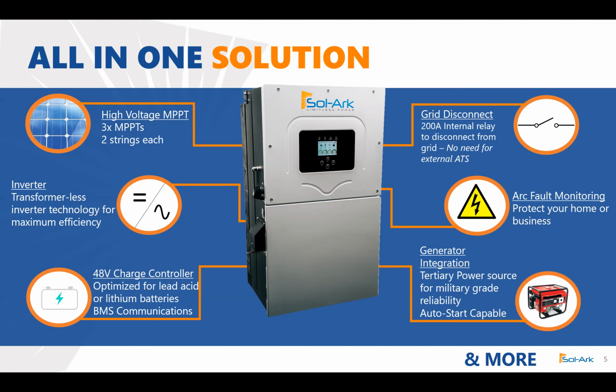We have an adaptable 48-volt charge controller that is battery agnostic. You can use any 48-volt battery solution with our inverter. Typically, the most commonly used today is lithium iron phosphate for its longevity and larger depth of discharge. But we can work with lead acid batteries, flow batteries, NMC batteries. Really, chemistry is your choice. As long as it's 48 volts, it'll work with us. And we do have a number of battery manufacturers that we partner with on our website. I think we're around 15 battery manufacturers that we have closed loop communications with, and I'll touch on that later. And we're continuing to grow. So hopefully we'll have your battery manufacturer of choice adaptable with our unit in the future.